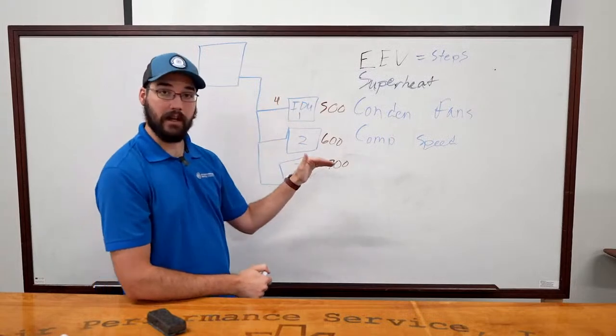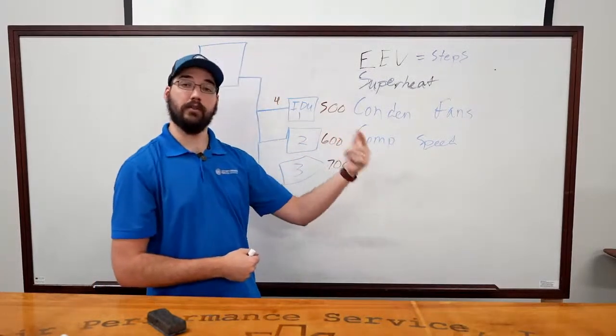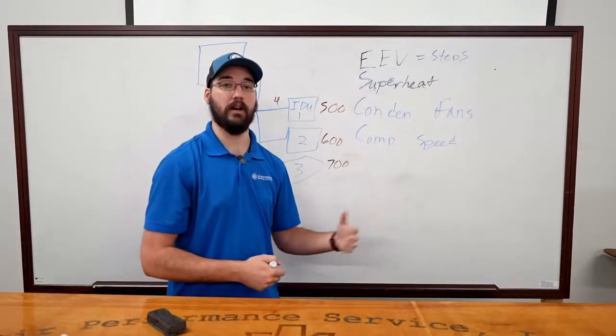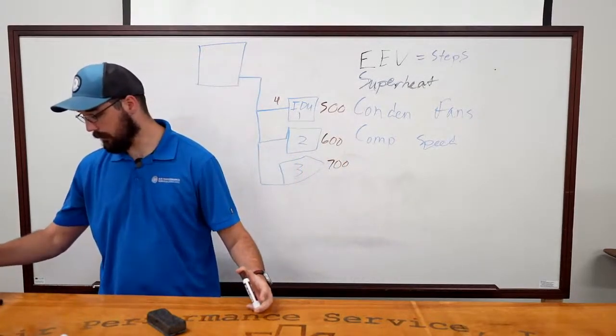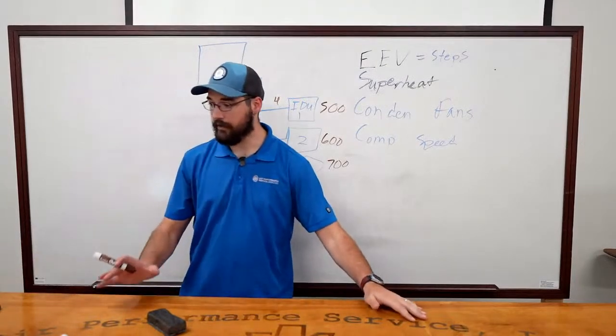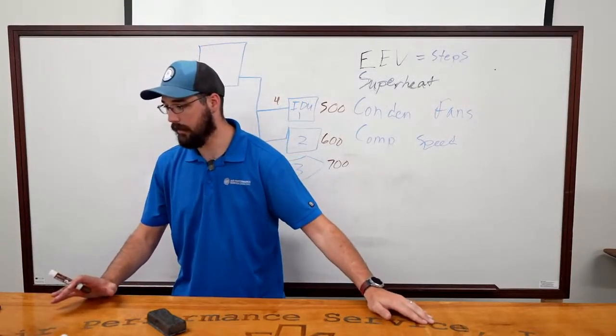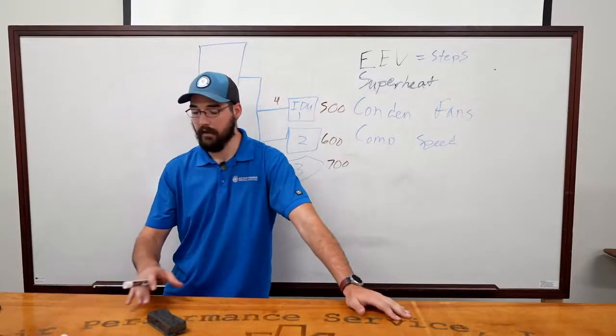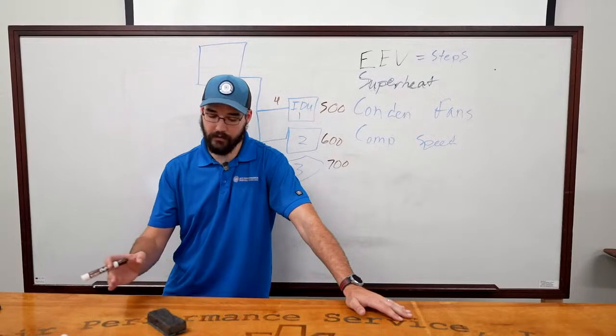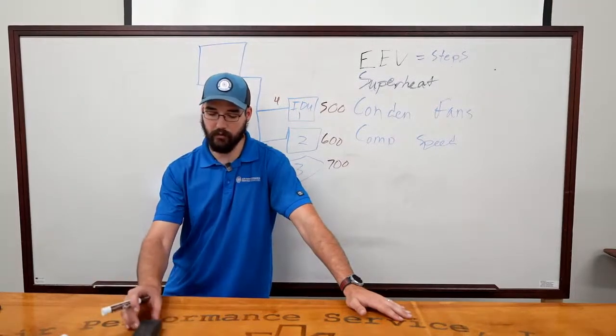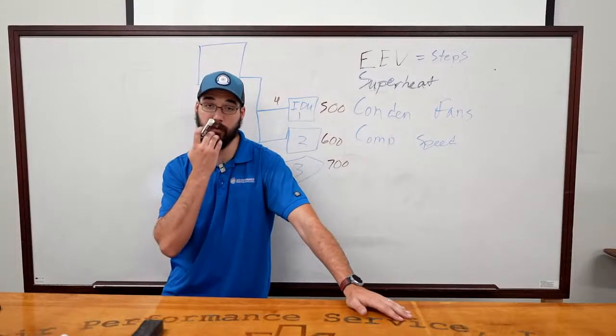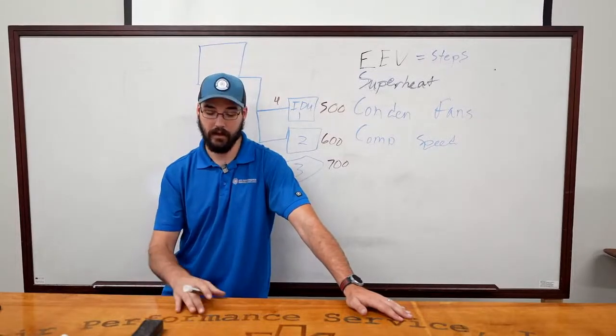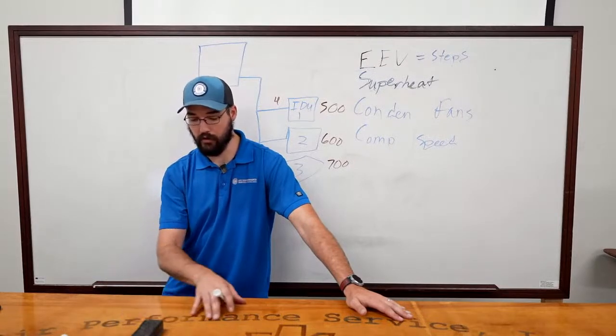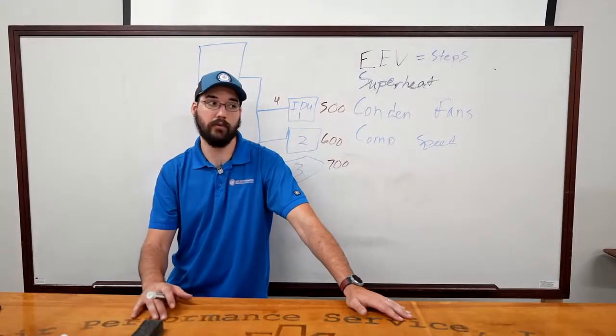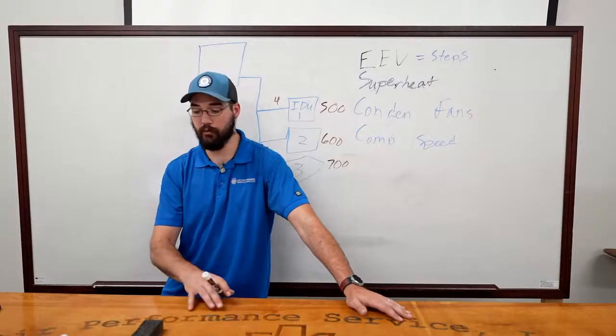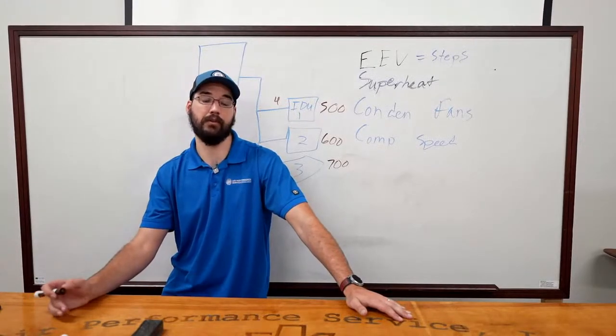And if they're still not where you like them, add 1 more pound. And you're going to do that, and you may be there for several hours doing this process. And that is something I do want to talk about a little bit. When you're dealing with this, the customers, especially if they don't have experience with a building that has VRV equipment, they're used to service calls that run 1, 2, 3 hours, and you could pretty well do the majority of what you'll ever need to on that machine in that short a time frame.